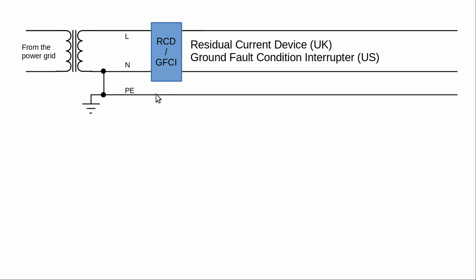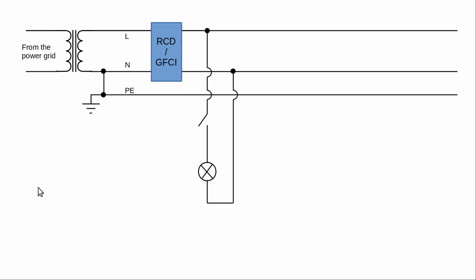And this is why we have this separate wire here, because this is where we draw the power from. And if anything else comes back through the earth, either through the earth itself or through the PE wire, then this will indicate a fault condition, and we will see this later in the video. Let's add a very simple lighting circuit to this. We put in a light bulb, and the light bulb is switched with a switch, and the switch switches the live wire. Power goes through live, through the switch, through the light bulb, and back to neutral.